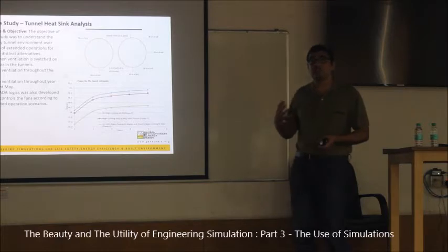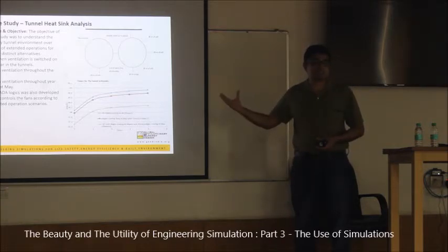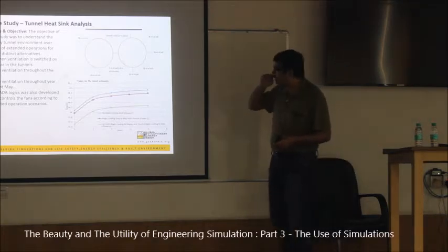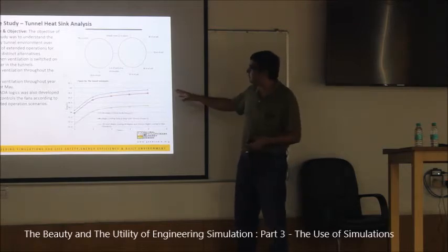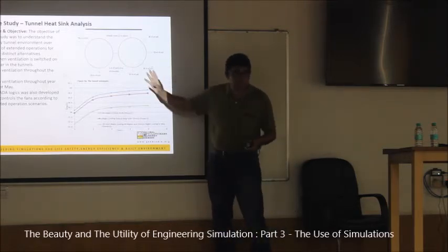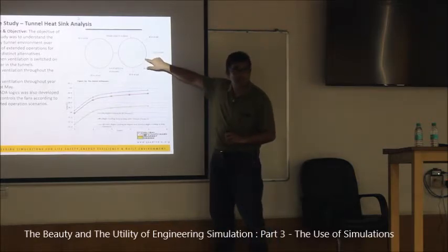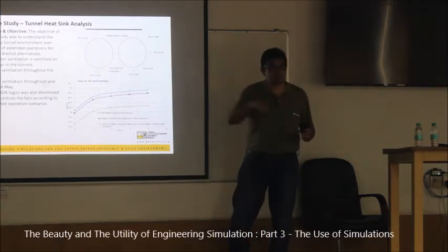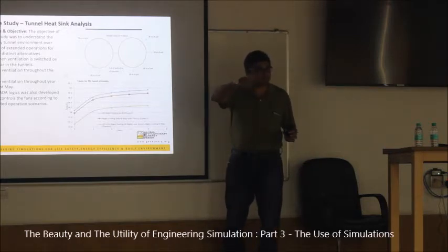What you need to do is simulations. You have to do real-world simulations to understand and predict whether these things are within range or not. So we did 25-year simulations for understanding this. Let me quickly list the phenomena. There is convection happening here, and there's forced convection also. When the train comes, velocity increases, so there's a term called the Nusselt number, which keeps on updating.